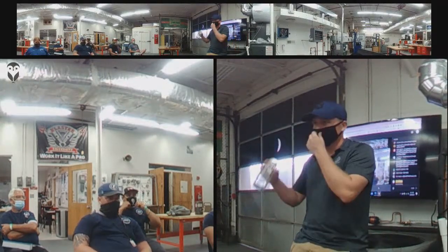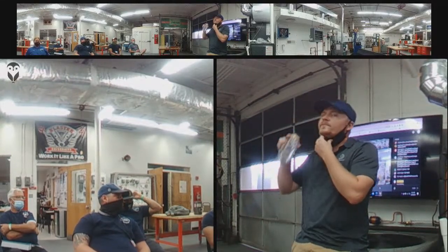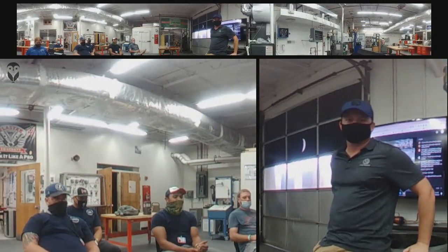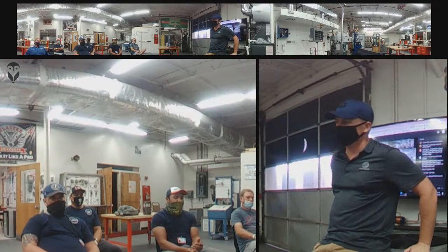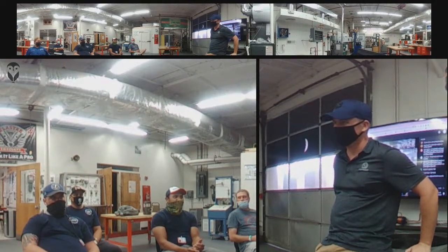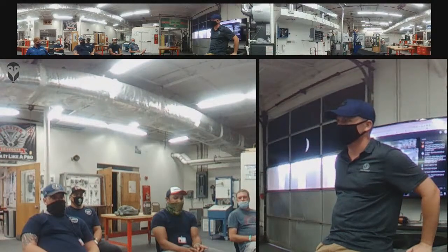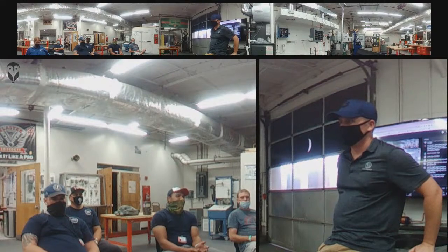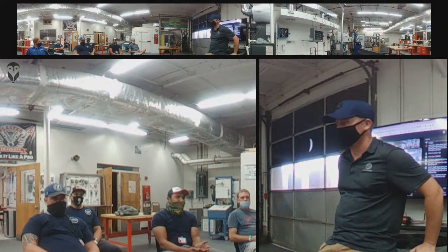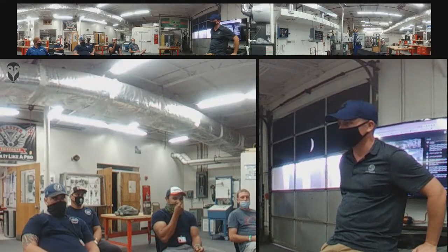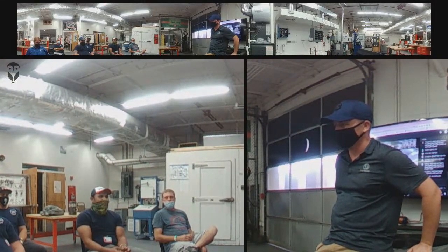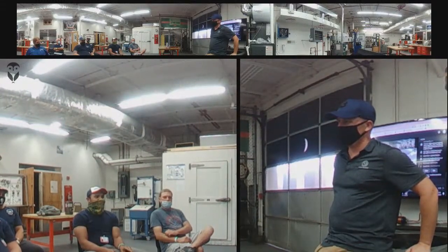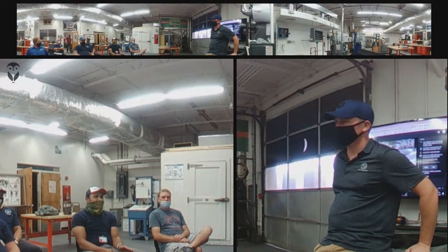Monday morning, like 3:15, I got a call for Security 1. The whole rack was down for the frozen foods on the high section, and all the compressors except for one were on high pressure lockout, so they wouldn't run. I found one of the fans on the condenser rack was down. It was weird, because I guess when it went out, it backfed to the board, because I had power at the board but not to the fans. It was really weird.